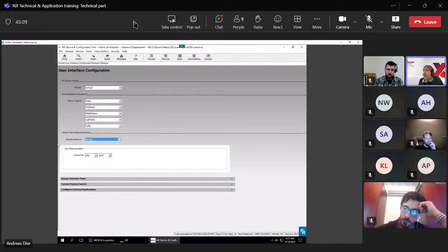Then the next part, unit representation. So you see here it talks about dose area. This is the dose area product unit. In fact, this is required if a dose area product meter is used, which is the sensor or radiation measurement chamber, placed between the collimator or below the collimator in direction of the patient, to measure how much dose for that appropriate area comes out of our tube.